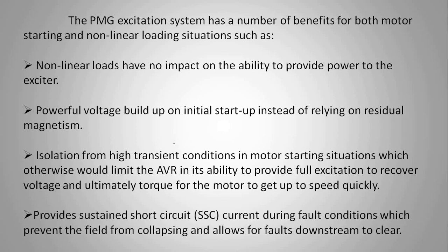It also provides sustained short circuit currents during fault conditions. Here the fault clearing time is very low, because the AVR will act as fast as possible when it is fed from a separate source, not from the stator generating voltage. So these are the main advantages of having PMG excitation. Thank you.